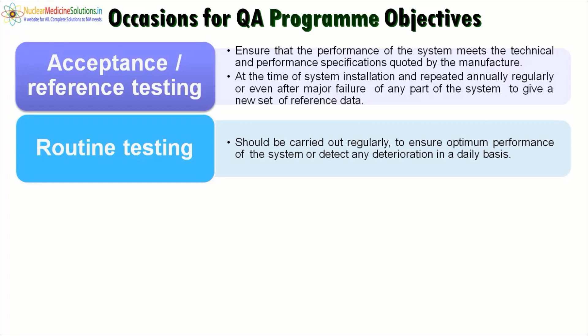And if we see any change in the value from the reference value, then we take corrective action to correct it. We also maintain the record of all these quality control tests to see how deterioration takes place in the future. So by doing the quality control tests, we are fulfilling the expectations of the physicist in terms of the instrument, that my instrument is working properly and there's no problem; the clinician in terms of the image, that whatever image the clinician is getting is free of any artifacts due to the instrument; and the patient in terms of the report, that whichever report the patient is getting is perfectly okay.